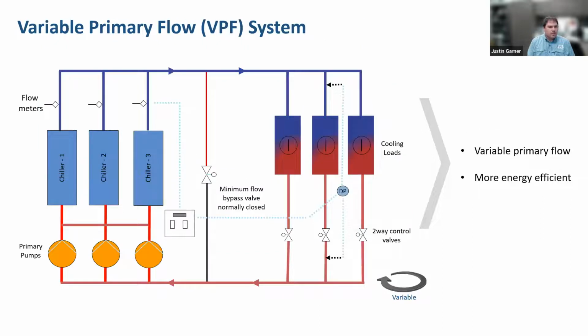So then we get to where we are in most newer systems today. And it's typically full variable primary flow. Many of our chillers today can vary their loading much more easily than they used to. And so nowadays, we see where we have primary pumps that are on variable speed drives that pump out into the remote loads. But you do still have to have a bypass.